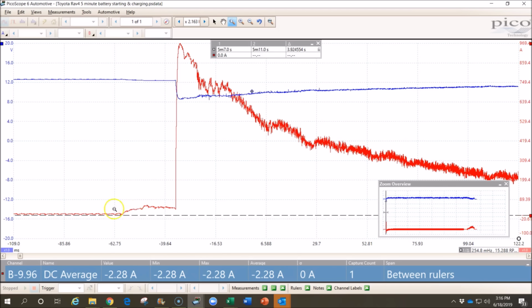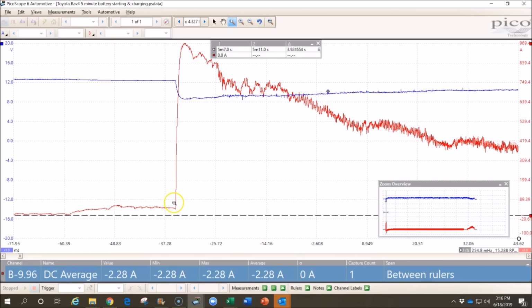Now it's different on different waveforms. Typically you'll see a little bump right here. This bump represents where the solenoid actually began to move. So this was ramping up and we got enough current that right here at this point the solenoid began to move, and then right here the contacts closed. So we can see, if we want to pull this down, we can see that the starter solenoid used approximately 46 amps.